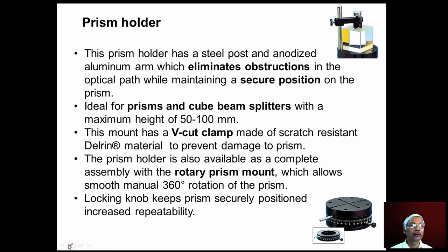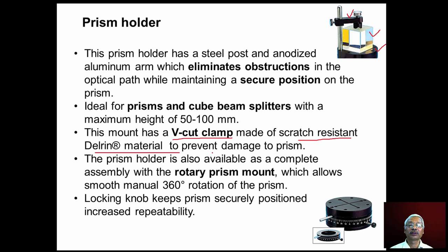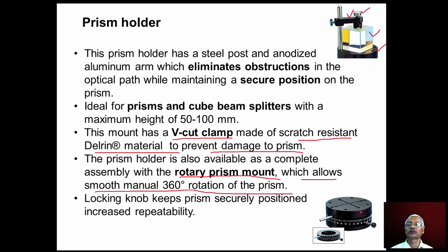Appropriate prism holders should be used. The prism is mounted on a flat surface with a vertical pillar and a V-cut clamp made of scratch-resistant Delrin material to prevent damage to the prism. A screw clamps the prism properly. A rotary prism mount allows smooth manual 360-degree rotation, enabling adjustment of the prism inclination.